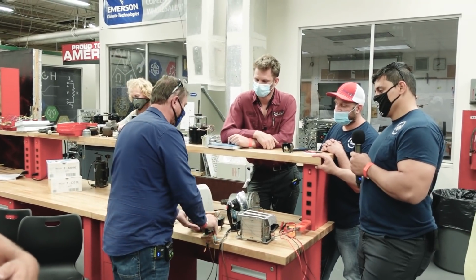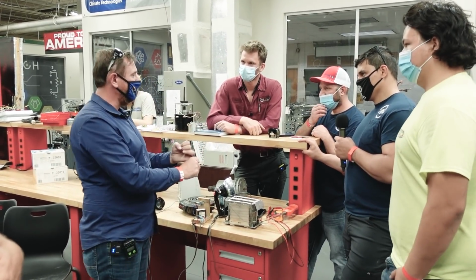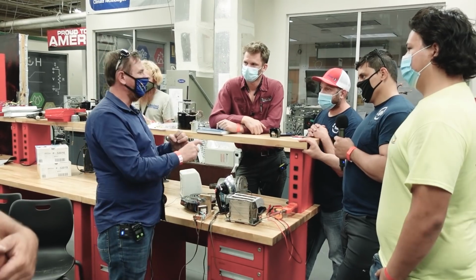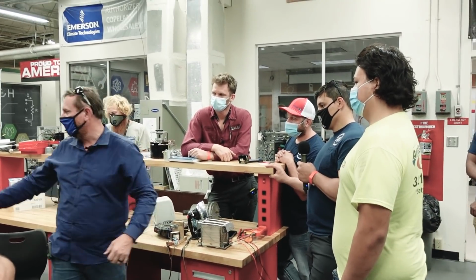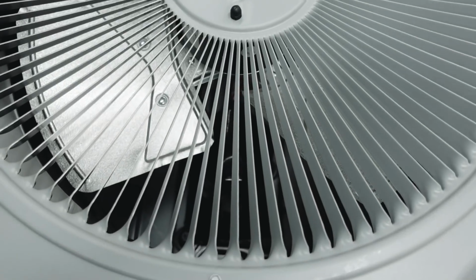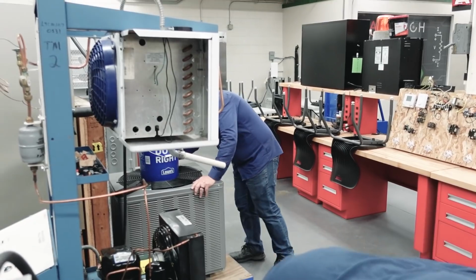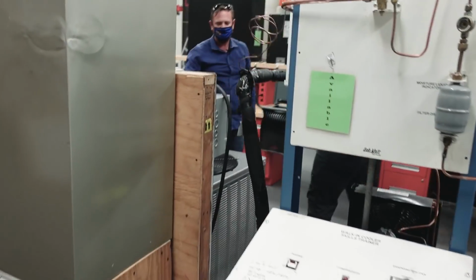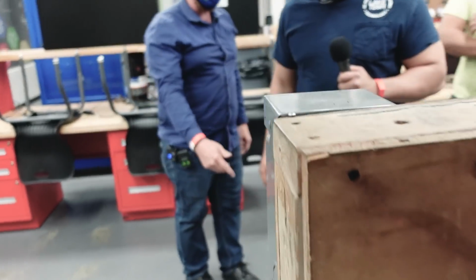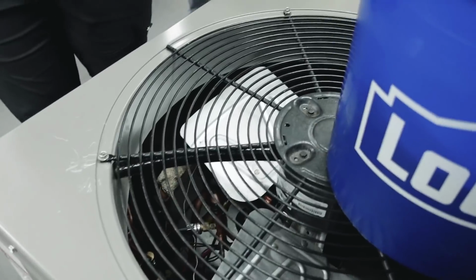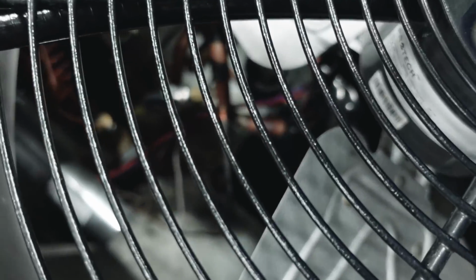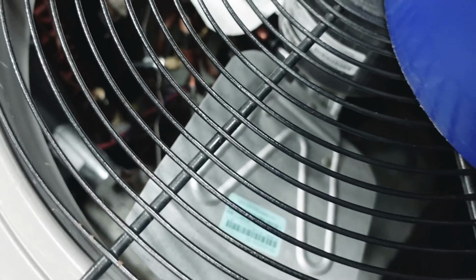Now, what killed it is going to be either a short to ground, like a wire rubbing through a cabinet, the wires inside the condenser. Look over here in this condenser, do you see any wires in there? This one's even better, look inside, do you see any wires? The compressor wires. There's a high pressure switch, a low pressure switch, a solenoid for reversing valves. There's all kinds of wires in there.